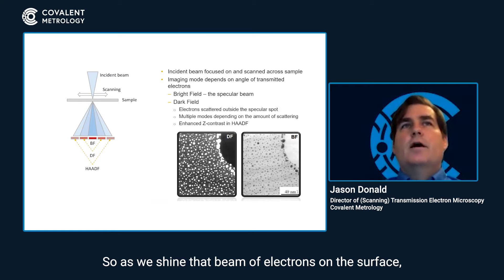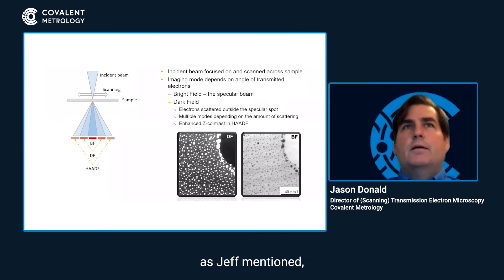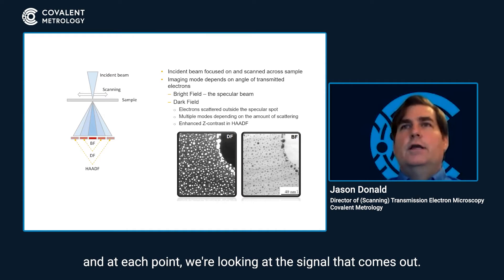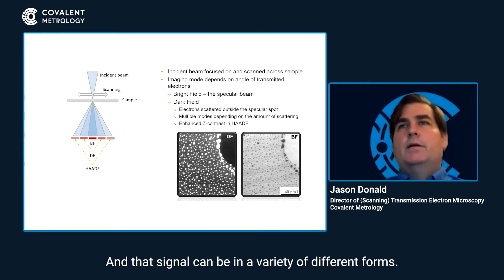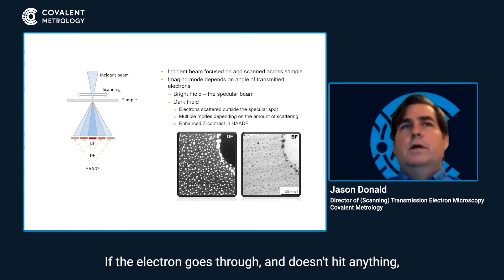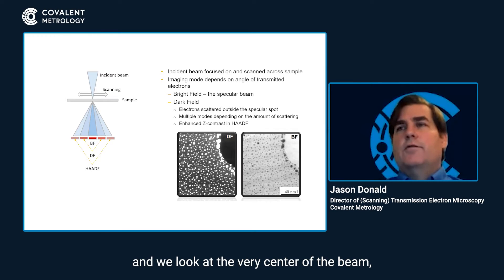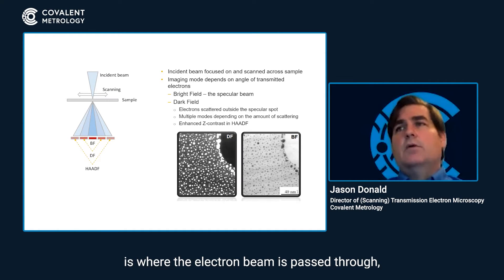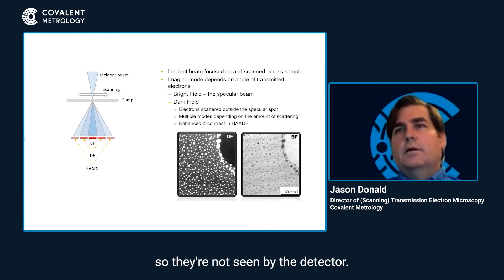As we shine that beam of electrons on the surface, we're actually rastering it right and left, up and down in a pattern. At each point, we're looking at the signal that comes out, and that signal can be in a variety of different forms. If the electron goes through and doesn't hit anything, and we look at the very center of the beam, we get what's called a bright field image. Where it's bright is where the electron beam has passed through, and where it's dark is where we see scattering — those electrons were knocked out of the path and are not seen by the detector.